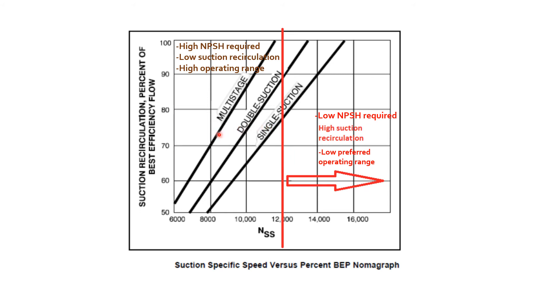If we have a pump with NSS less than 12,000, what happens? The disadvantage is that NPSHR shall be high, as we talked about the inverse relationship. The advantage is that there will be low suction recirculation for the low NSS number. Third, the operating range for the pump will be high.